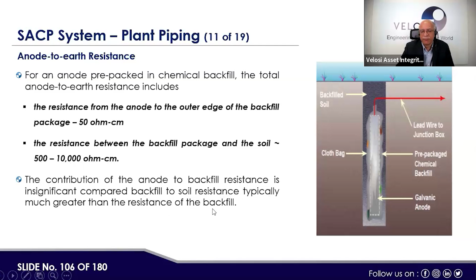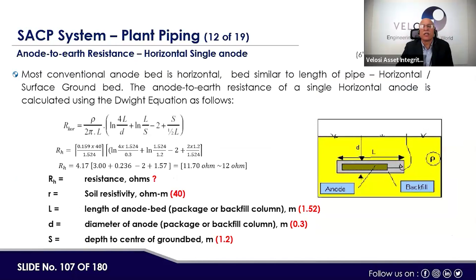The resistance between the backfill package and the soil may vary from 500 to 10,000 ohm-centimeter. The contribution of the anode-to-backfill resistance is insignificant compared to the backfill-to-soil resistance, which is typically much greater than the resistance of the backfill. Here, for the anode-to-earth resistance of a horizontal single anode, this is the formula and we can calculate it.